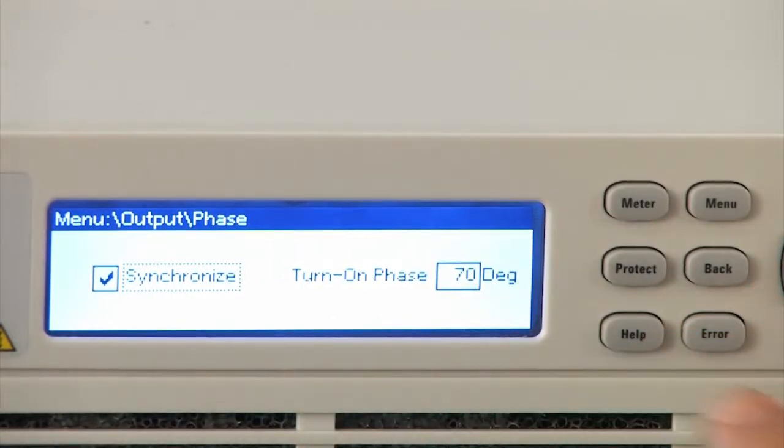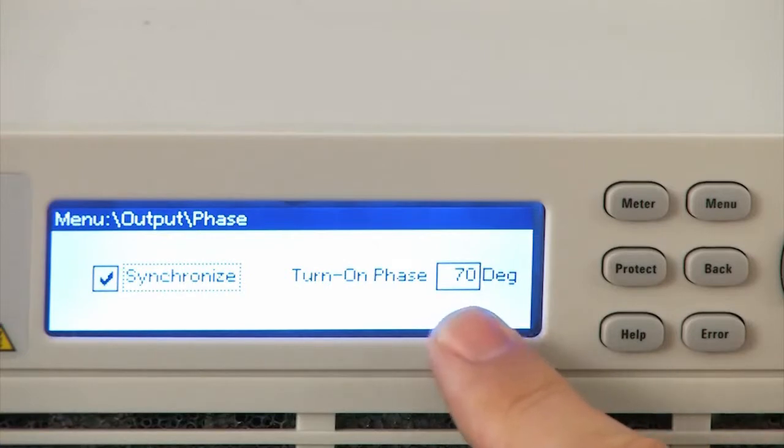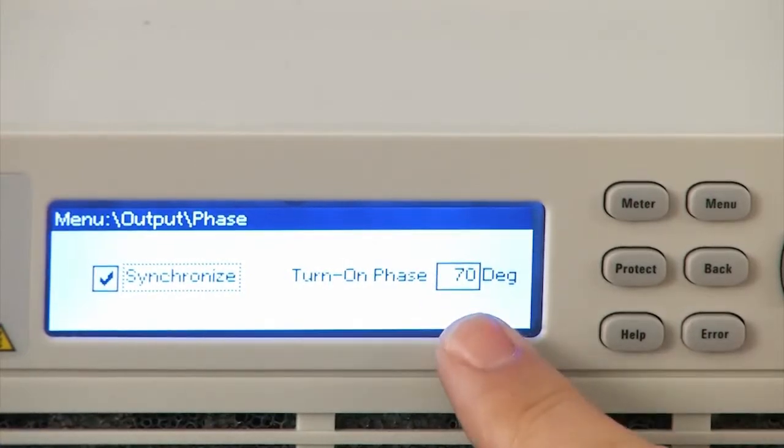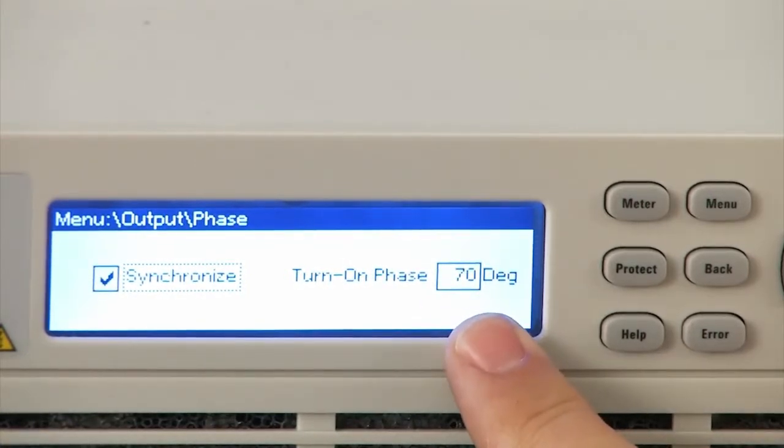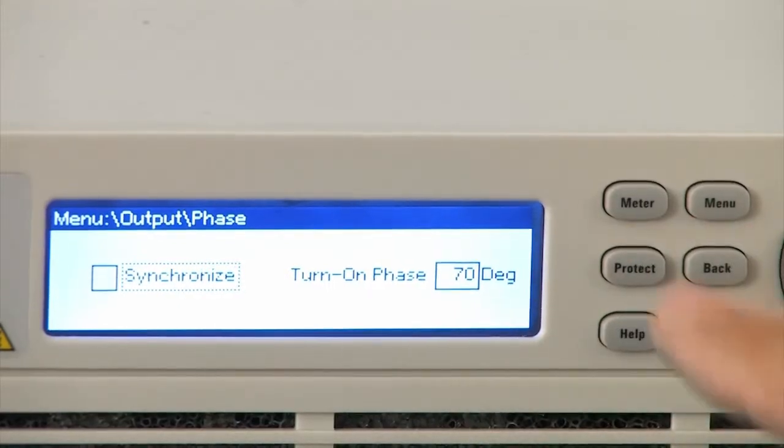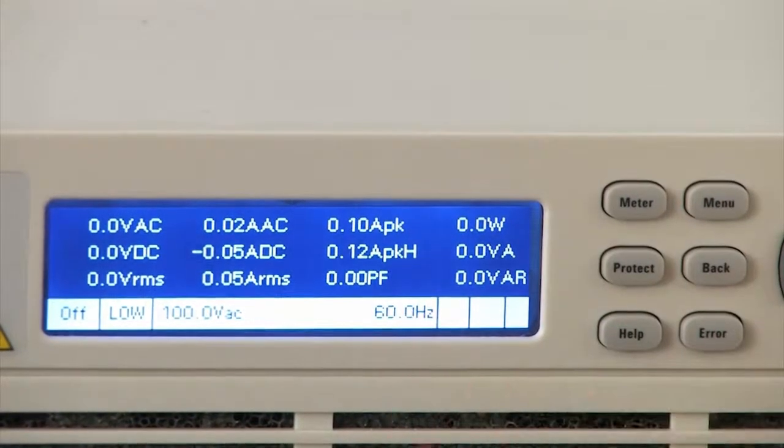You can actually synchronize the output turn on to be at any degree between zero to 360 degrees. I've chosen 70 degrees in the screen here, so all I have to do is say enter and go back to my screen.